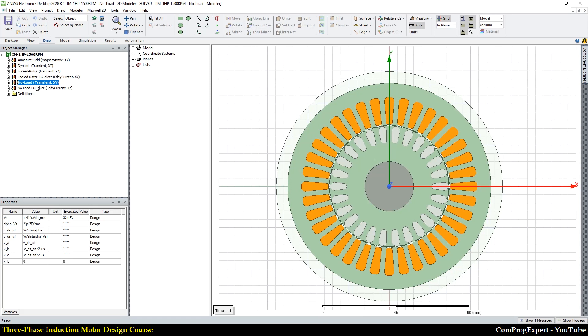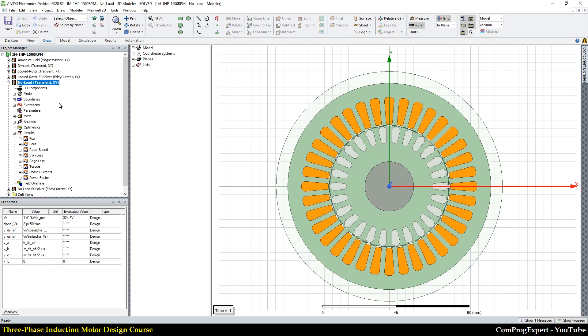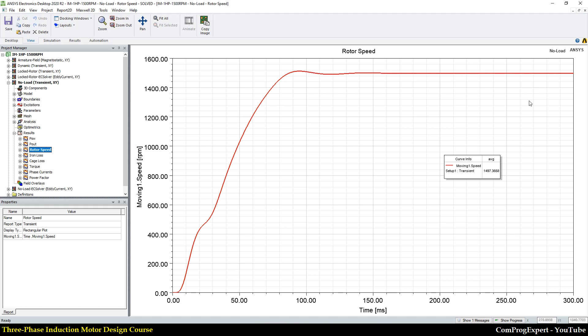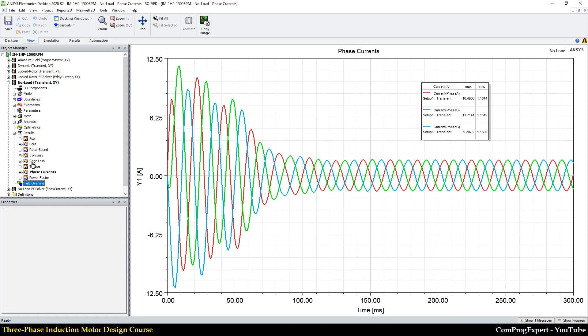We will perform both tests in the software. In the no-load analysis, we don't apply any load on the shaft, so the motor is free to rotate. Here you can see the rotor speed reaching near the synchronous speed in steady state — slightly lower because of friction. You can also see the phase current and power factor.